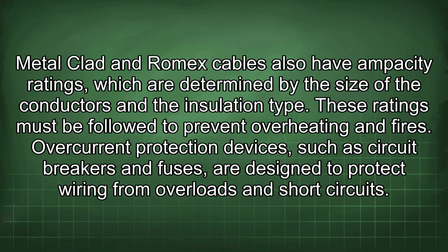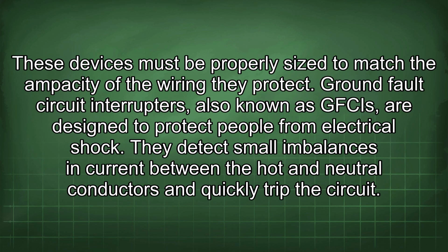Metal-clad and Romex cables also have ampacity ratings, which are determined by the size of the conductors and the insulation type. These ratings must be followed to prevent overheating and fires. Overcurrent protection devices, such as circuit breakers and fuses, are designed to protect wiring from overloads and short circuits. These devices must be properly sized to match the ampacity of the wiring they protect.